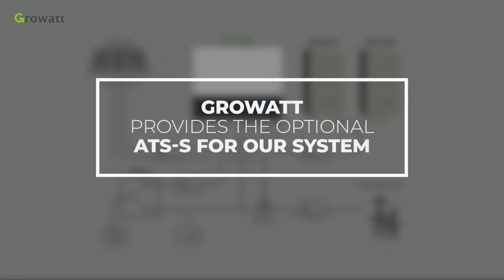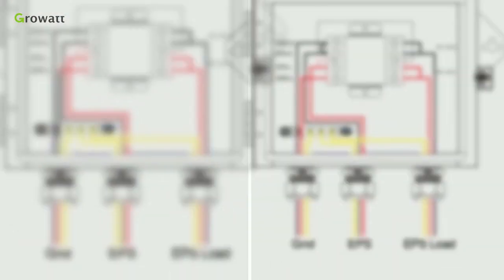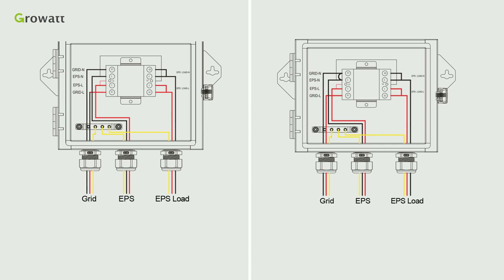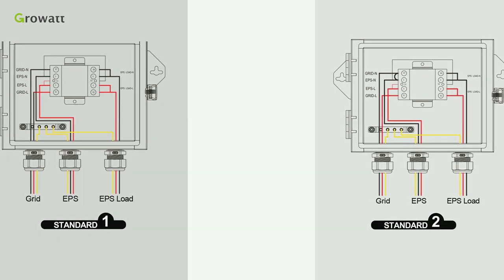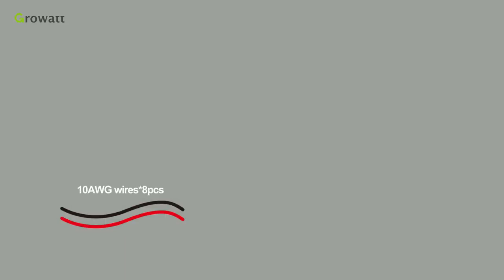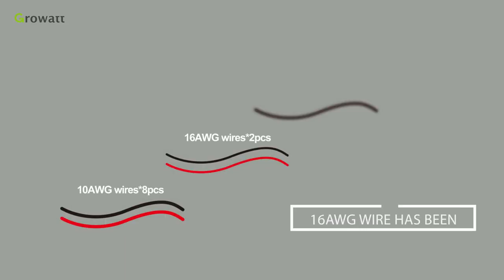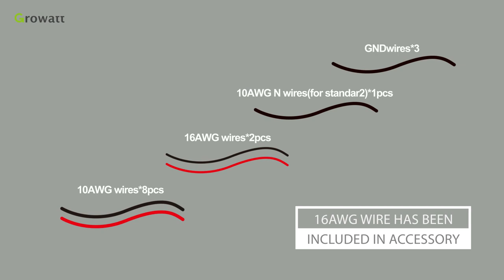If the customer requires the backup power function, Growatt provides the optional ATS for our system. We can follow the diagram to connect the ATS. Standard 1 is for general use and Standard 2 is for the market like Australia where the neutral line can't be switched. Wires are needed before installation. 16 AWG wire has been included in accessory.